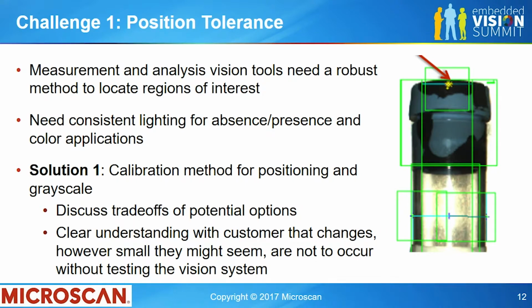In one situation, we have a customer that has an actual calibration fixture that they'll put in and calibrate at regular intervals. But that might not work for everyone because it adds cost and it adds complexity to the lab itself, to their customer. Another situation where we have a calibration target label that's placed in the field of view that has different contrasting colors as well as shapes for measurements, and that works well. But again, another customer can't use that because they need to do very strict cleaning methods within their instrument, and the material that would be needed for that label is very expensive. In that case, we came up with a way to actually make marks or holes within the sheet metal itself so that we could track to that mark, and that's how we're calibrating. So a lot of different methods to do it. You guys do many different types of calibration as well, but again, something that you really need to be working with that manufacturer on because it affects the design of their system, and they may have requirements that they didn't even think about.